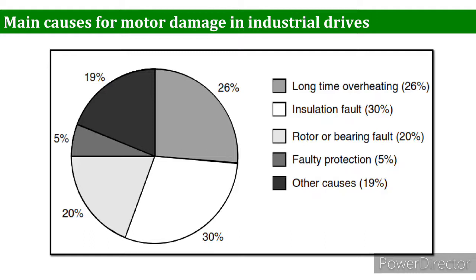Next, we look at the protective functions needed to detect motor drive faults. This important data was collected by the ABB Group, a major name in motor protection. From the graph, there are five main divisions: long-time overheating at 26 percent, insulation fault at 30 percent, rotor or bearing fault at 20 percent, faulty protection, and miscellaneous or other causes.